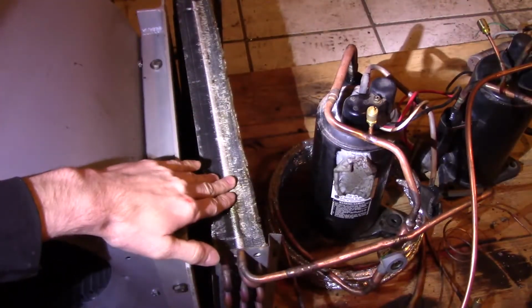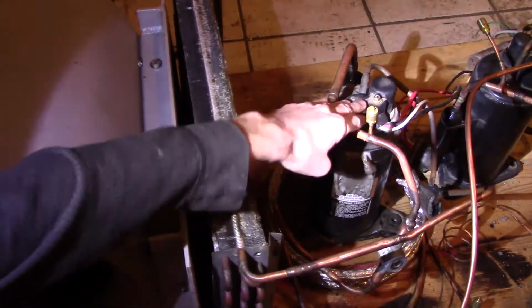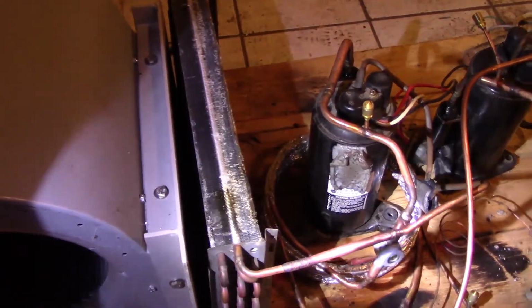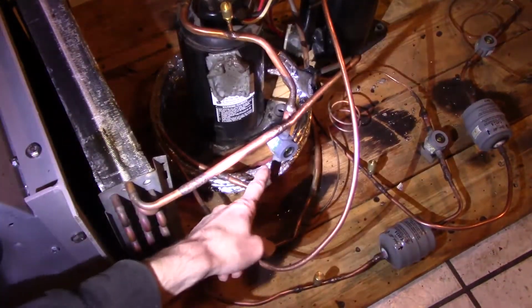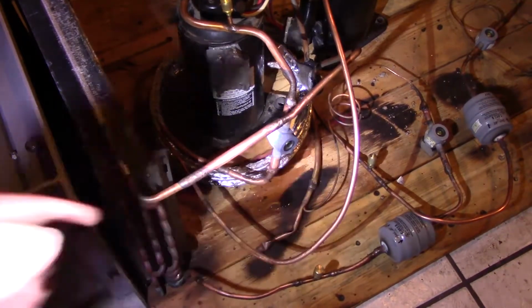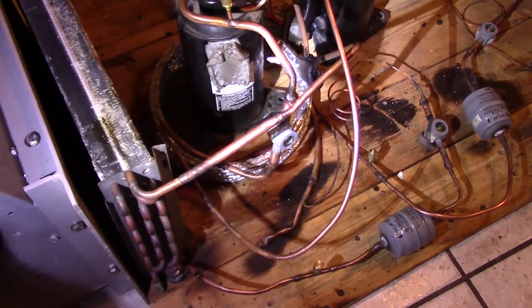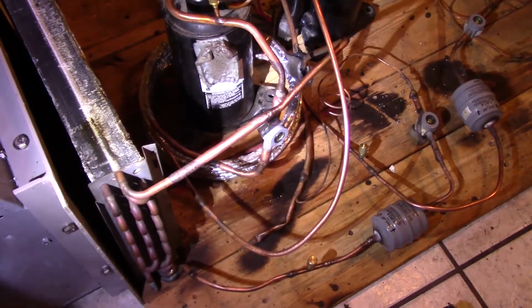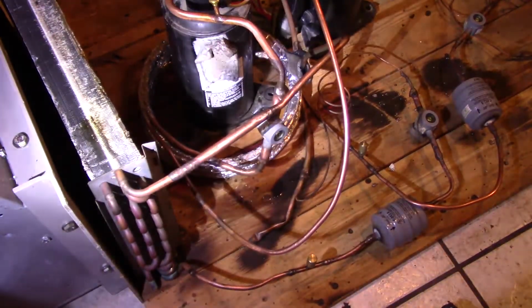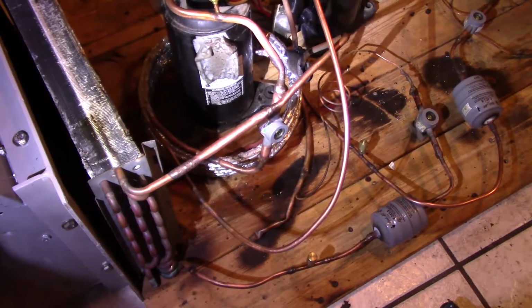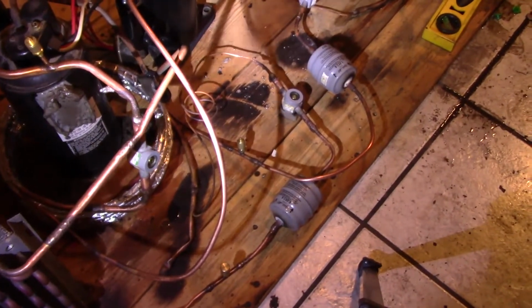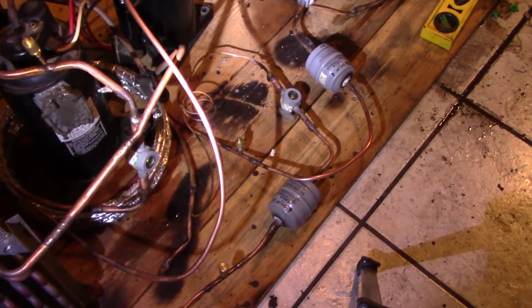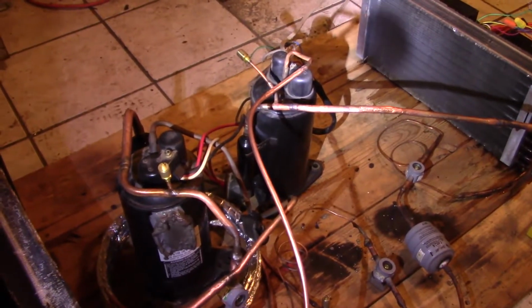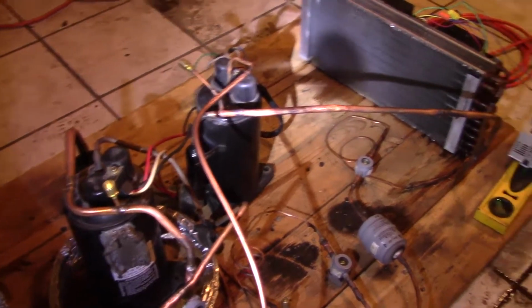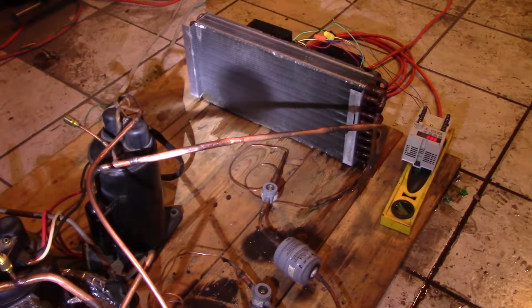this is the condenser of the high temperature cycle, and this is a compressor of the high temperature cycle. I have a sight glass here on the suction side for the high temperature cycle. Cascades are kind of dynamic, and if you don't get the charges right, you'll get liquid back into the high cycle compressor real easy. So you need that sight glass just to keep an eye on things. And obviously we have filters and sight glasses for the liquid lines for high and low temperature cycles. Now that other compressor over there obviously is a low temperature cycle compressor. That's the evaporator over there.